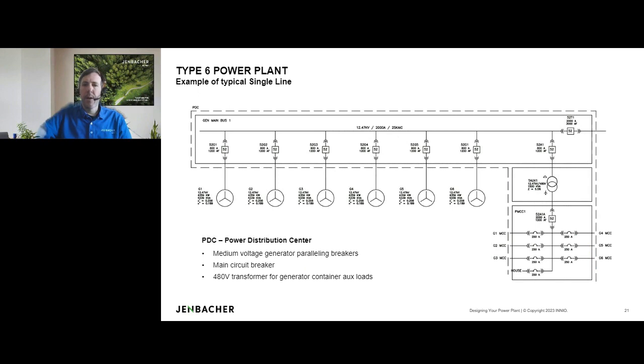This is a typical single line of the power distribution center which would be needed. You have the generators lined up next to each other. Then in the power distribution center you would have your medium voltage - 13.8 or 12.47 or whichever voltage it might be - breakers lined up on a common bus. You would have one auxiliary breaker feeding a step-down transformer to 480 volt, which would feed the auxiliaries of the containers that need 480 volt, like the radiators and so forth. And then you would have your main connection, your tie breaker right over here.